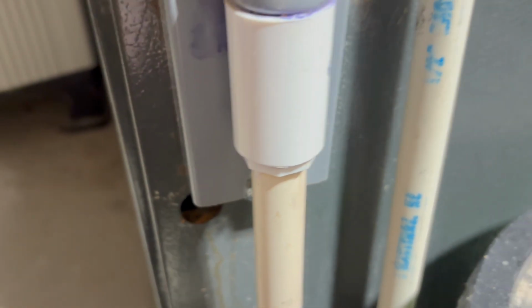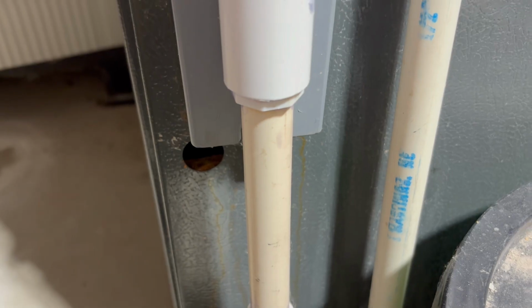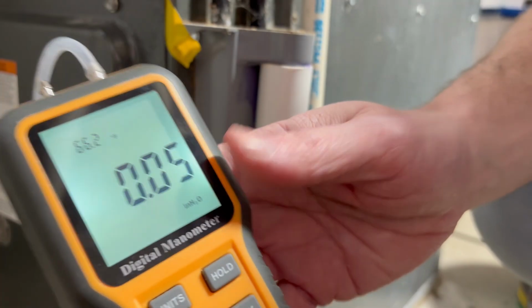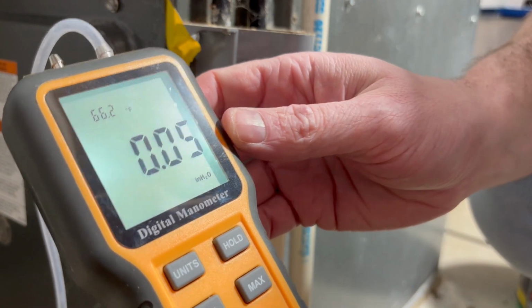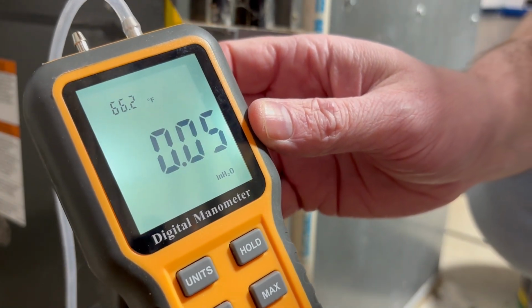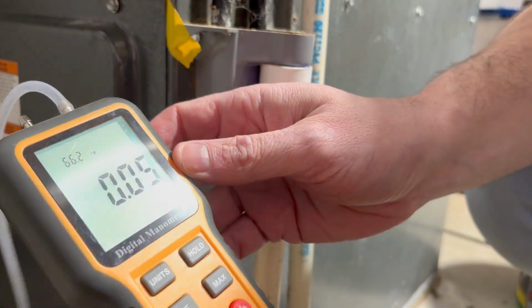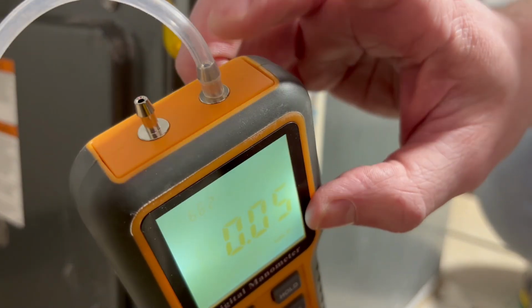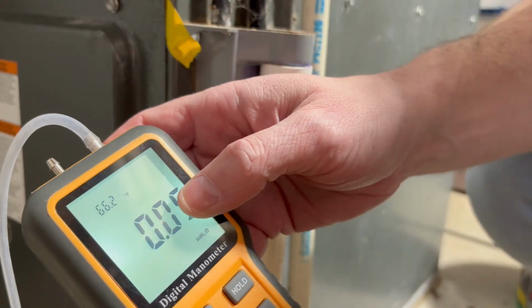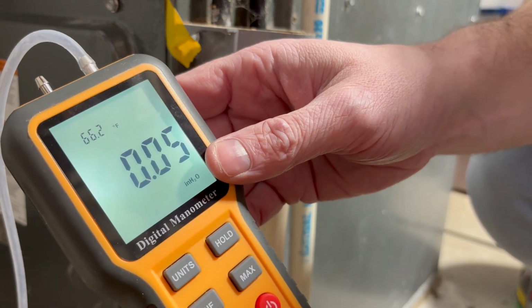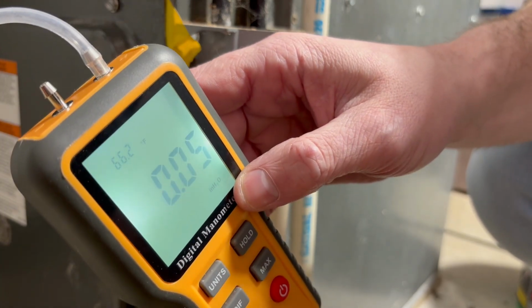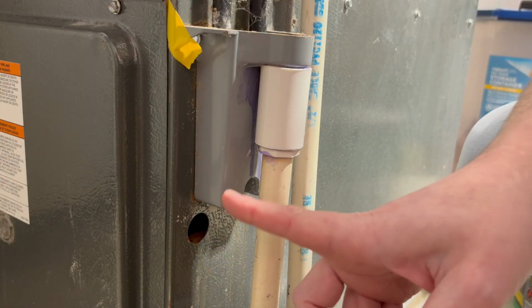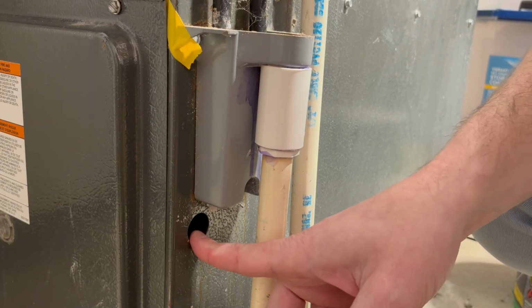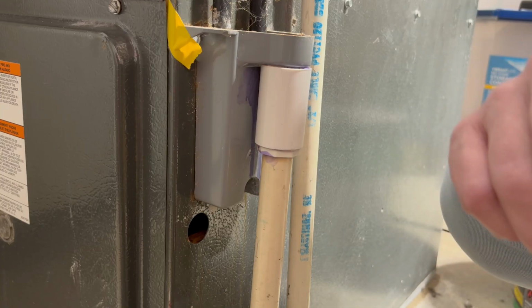We're not really concerned about absolute values. We're really just trying to compare, as we switch between filters, what sort of change we are seeing. And if you've never used a manometer before, it may sound a little more complicated than it actually is. They're relatively simple to use. This one was 30 bucks on Amazon. It's a very basic one, but it has 2 ports at the top. So I could actually be taking 2 measurements at once, and it'll calculate the differential between the 2 static pressure readings. In my case, I'm only going to be using 1 port because I'm really just interested in measuring the suction side static pressure so that I can gauge the impact between the different filters.